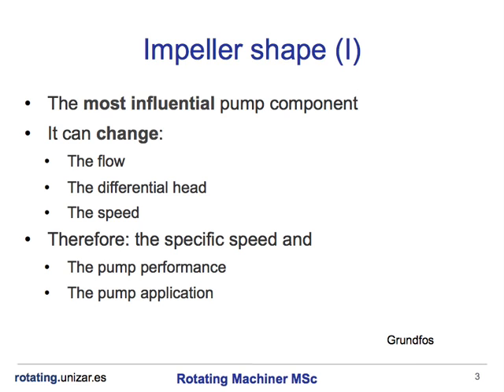The impeller is the pump component that has the most influence on pump performance. Actually, you can create a brand new pump by just modifying the impeller. It can change the flow, the differential head, the speed, and therefore the specific speed, the pump performance, and the pump application.